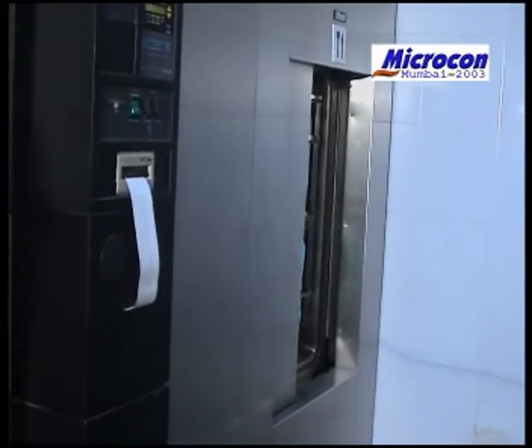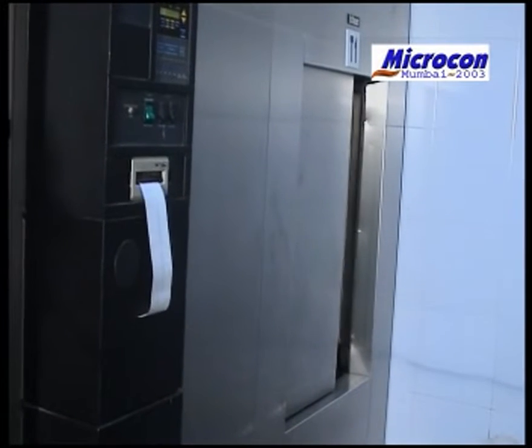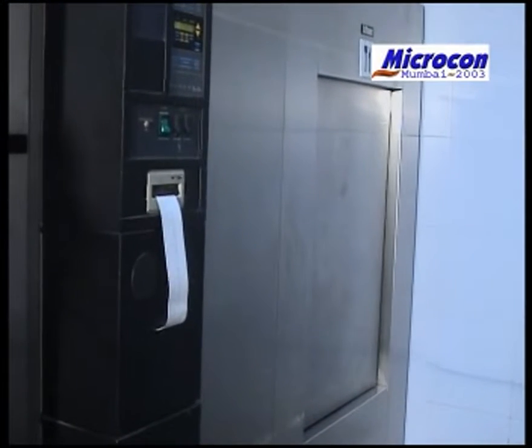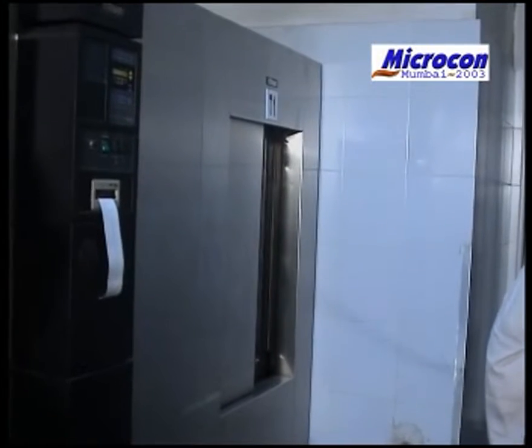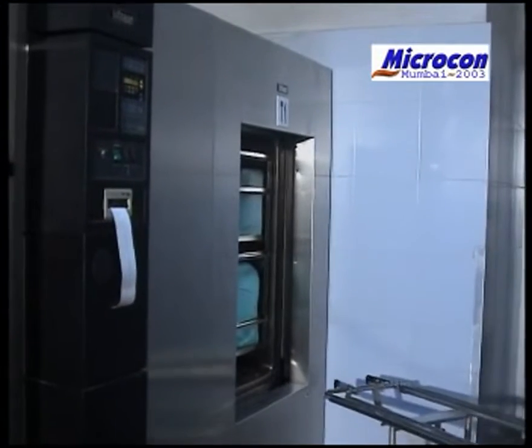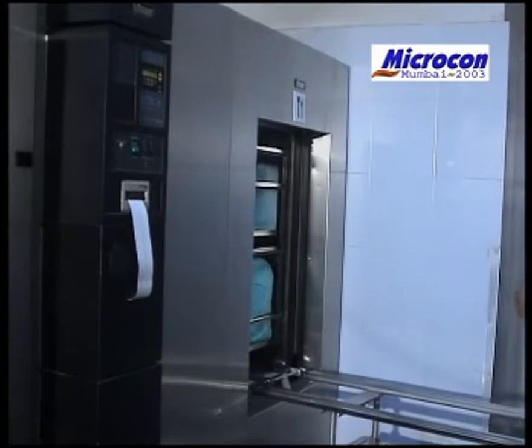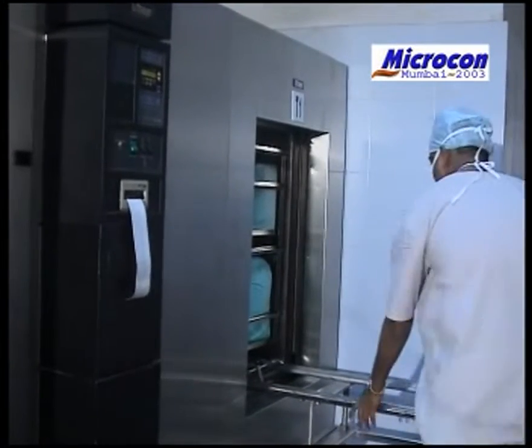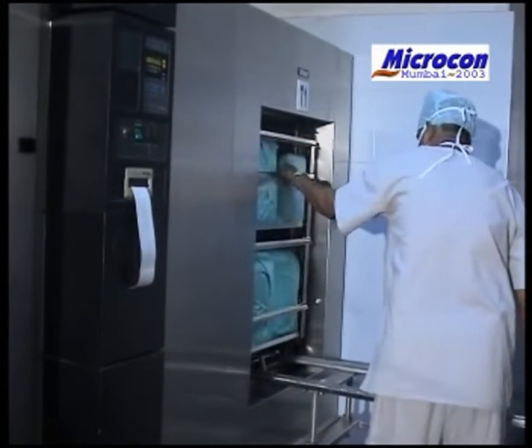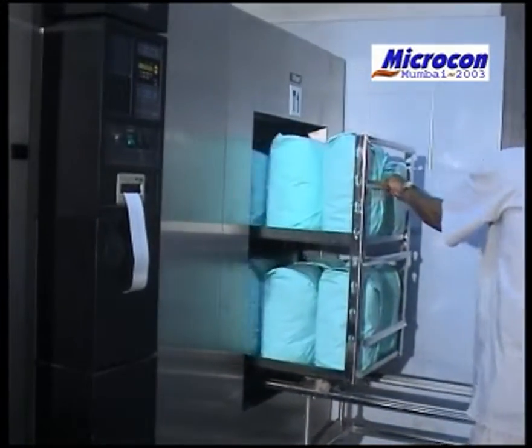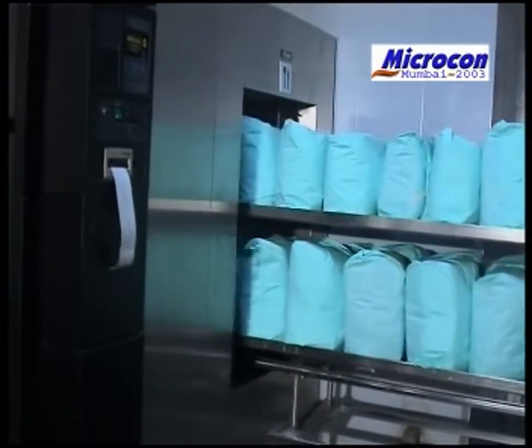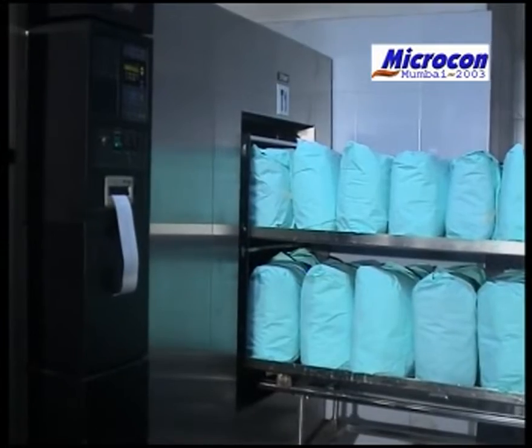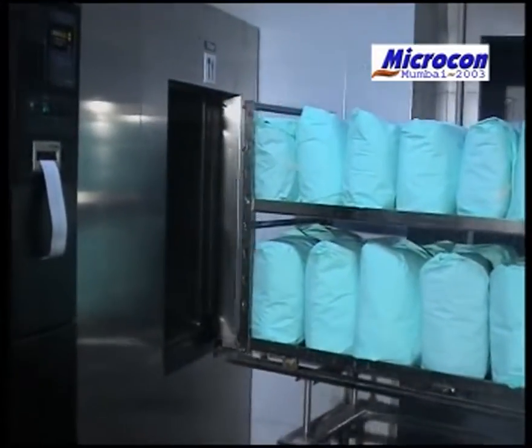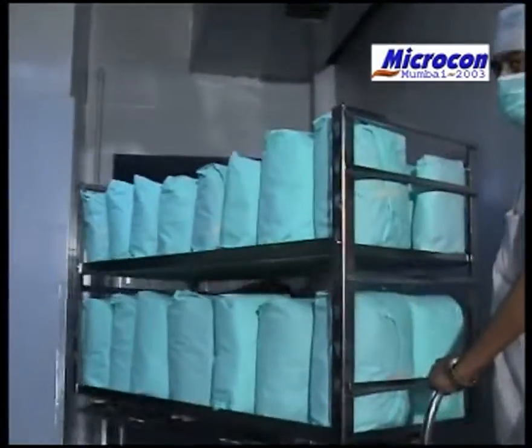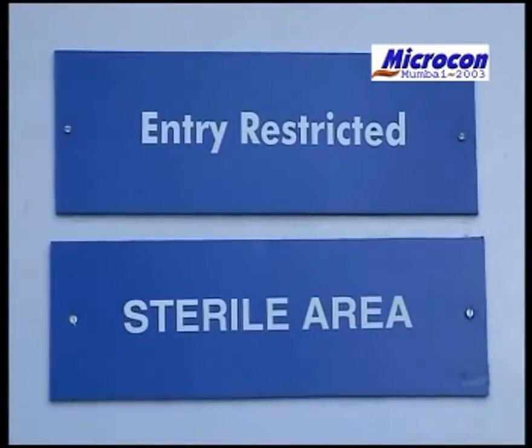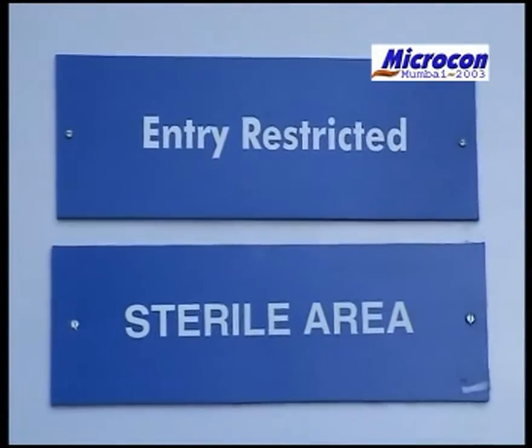Once the loading operation is complete, the sterilization process begins, and depending on the temperature of the sterilization process, the time is also controlled. The minimum standards are a temperature of 121 degrees Celsius and a pressure of 15 pounds per square inch with a sterilization time of 15 to 20 minutes. The sterilization process also includes a drying cycle. The unloading operation is carried out into a sterile area.